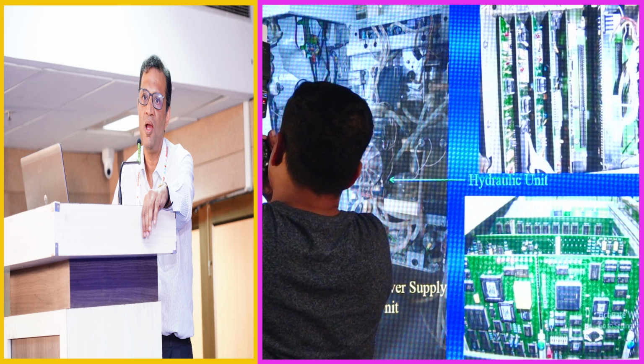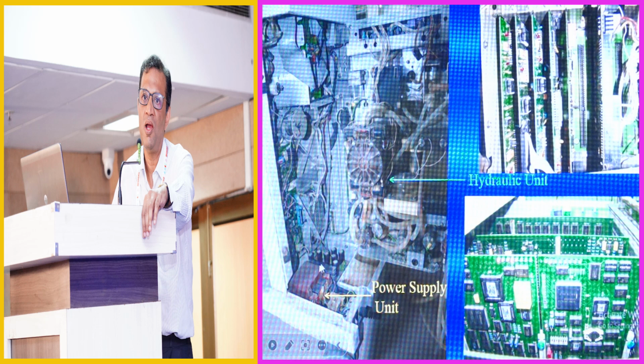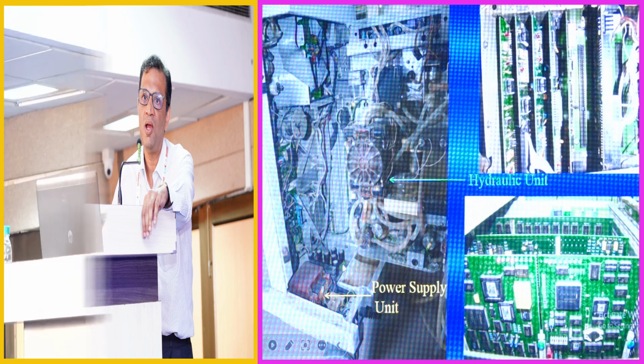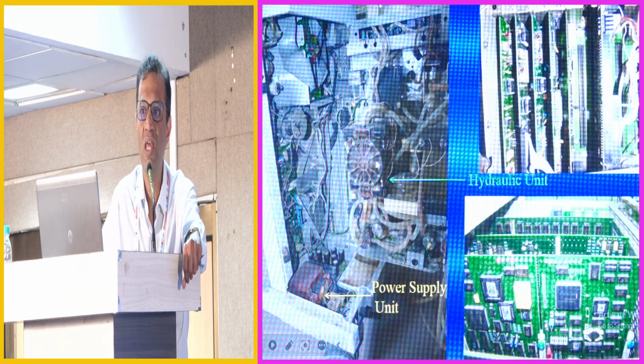Now, this is actually my favorite machine, which I have opened from the back. This is Althin's UltraTouch 1000. But where Fresenius scores over UltraTouch is in this design. If you see the UltraTouch, the main power supply enters through the base of the machine, and the hydraulic unit is here above it when closed. So should there be a leak in the hydraulics, you could have water or dialysate dripping down onto your main power supply board. It shorts, and then you have a problem. The other part about Fresenius, which is superior, this is the top portion.